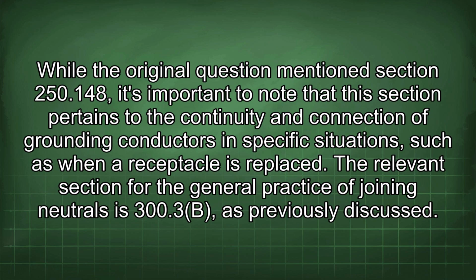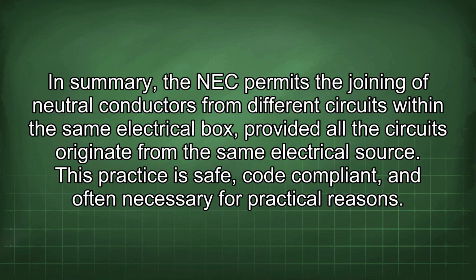While the original question mentioned section 250.148, it's important to note that this section pertains to the continuity and connection of grounding conductors in specific situations, such as when a receptacle is replaced. The relevant section for the general practice of joining neutrals is 300.3(B), as previously discussed. In summary, the NEC permits the joining of neutral conductors from different circuits within the same electrical box, provided all the circuits originate from the same electrical source. This practice is safe, code compliant, and often necessary for practical reasons.